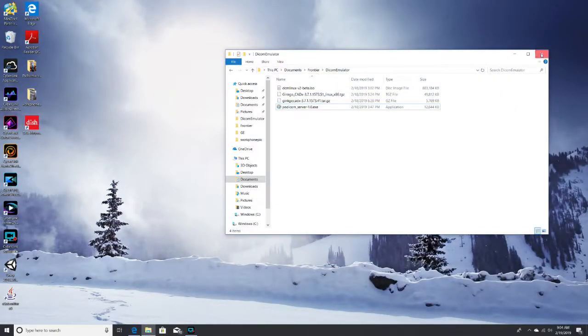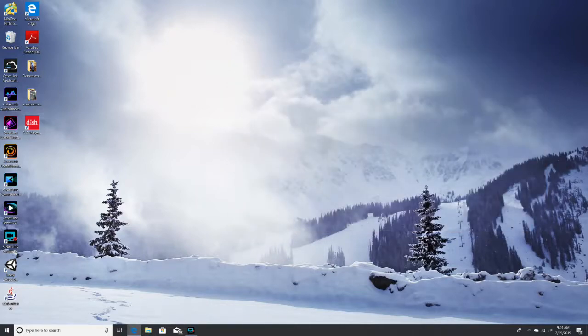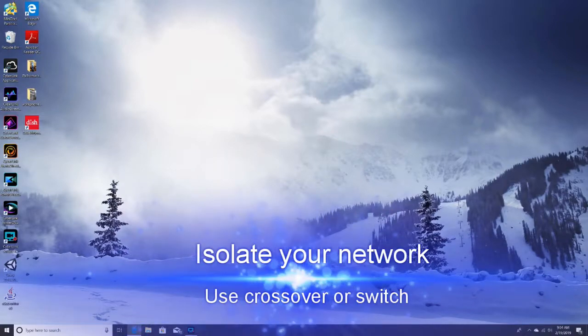Okay, before we can use this system, just a few prerequisites. You need to make sure that both of your systems are on the same subnet. Also, you need to make sure the IP addresses are just about the same except for the last octet. You'll want to isolate the machines, say it's a C-arm. You'll want to hook it up to your laptop or computer that you're using as an emulator through a crossover cable or a switch. That way there's nothing else that can be causing issues in between.